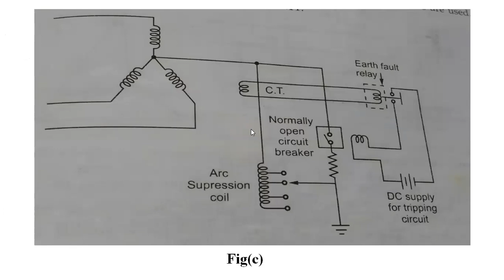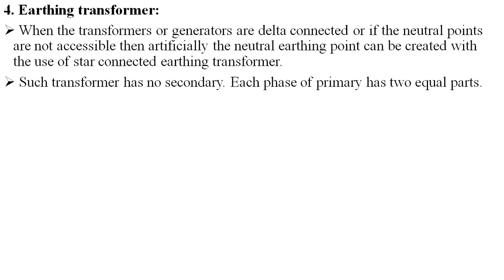Earthing transformer. When the transformers or generators are delta connected or if the neutral points are not accessible, then artificially the neutral earthing point can be created with the use of a star connected earthing transformer. Such a transformer has no secondary. Each phase of the primary has two equal parts. There are 3 limbs and each limb has 2 windings providing opposite flux during the normal condition.